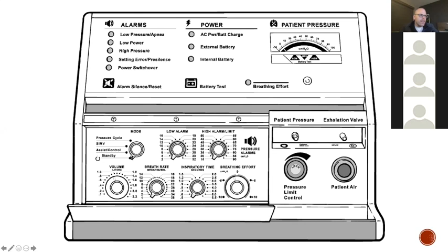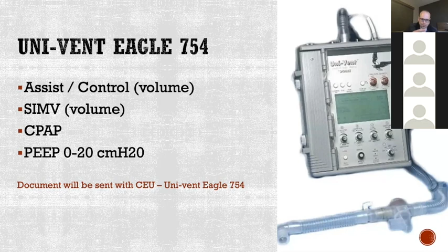The next ventilator in the Strategic National Stockpile is the Univent Eagle 754. This ventilator can do assist control volume and SIMV volume. It can also do CPAP. The nice thing with this one is it has PEEP built into it, so it can go from 0 to 20 of PEEP. So this one can do PEEP, but it's still not doing pressure modes of ventilation for us. What it looks like on the front, if we had to set it up in a pinch, and I will also send out the basic instruction manual for this as well. It'll come with your CEs.